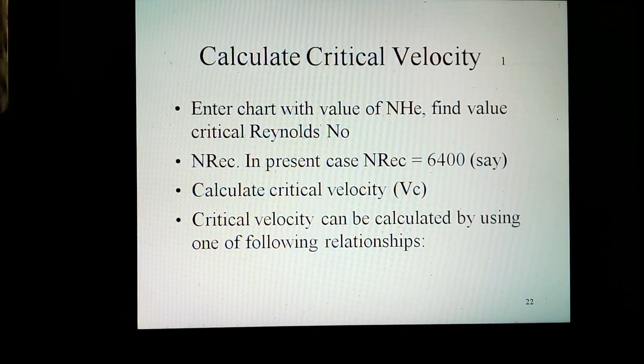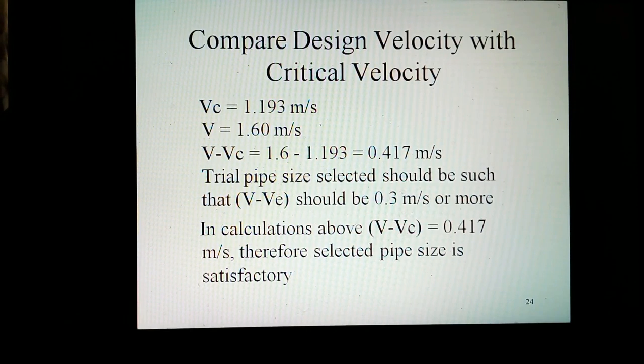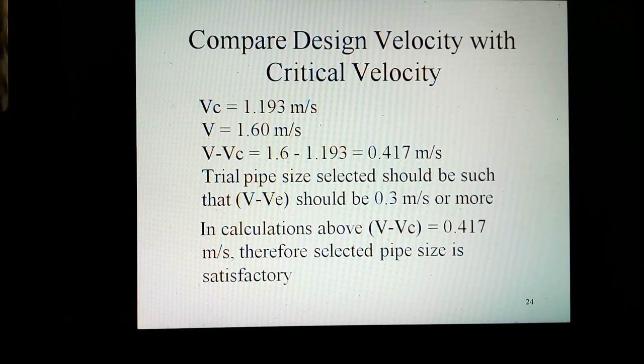Critical velocity can be calculated by using one of the following relationships. Comparing design velocity with critical velocity: V_c equals 1.193 meters per second. V equals 1.60 meters per second. V minus V_c equals 1.6 minus 1.193 equals 0.417 meters per second. The trial pipe size selected should be such that V minus V_c should be 0.3 meters per second or more. In the above calculation, V minus V_c equals 0.417 meters per second. Therefore, the selected pipe size is satisfactory.